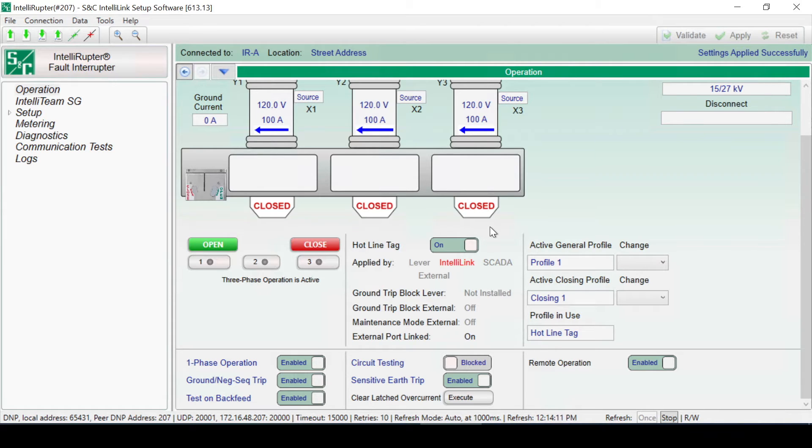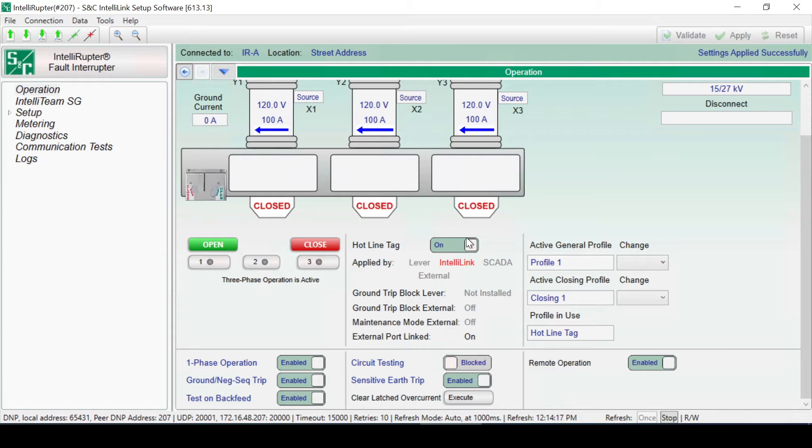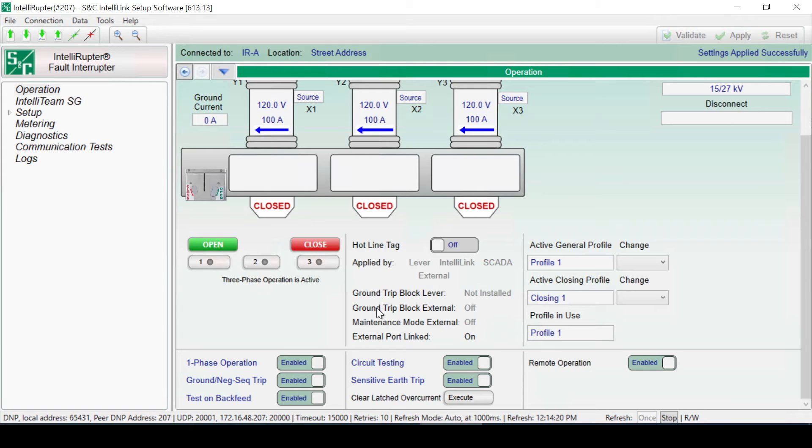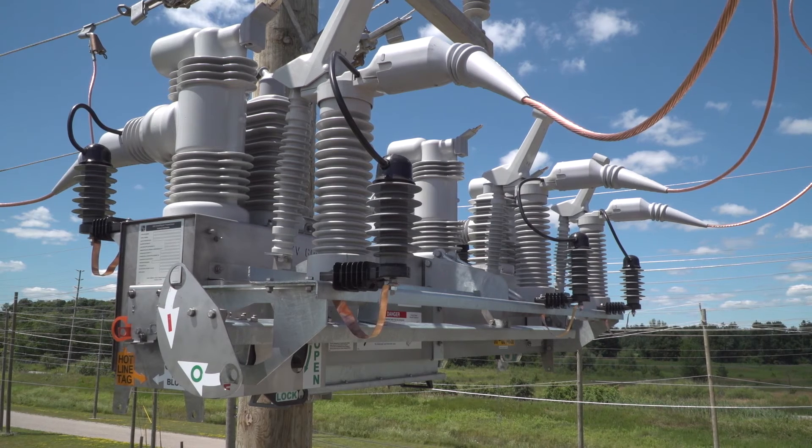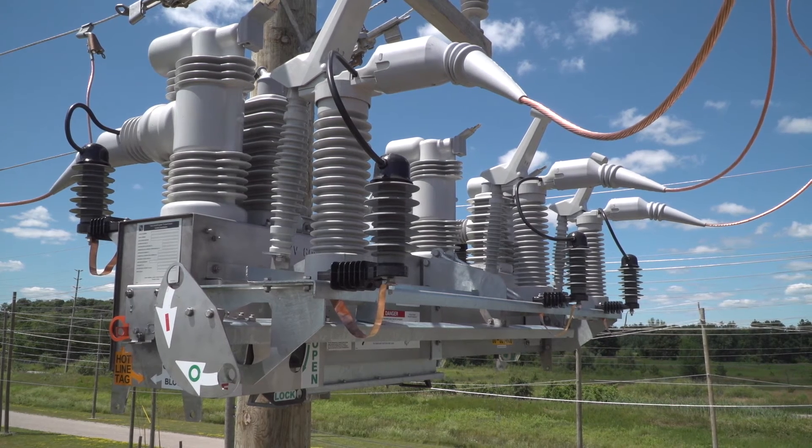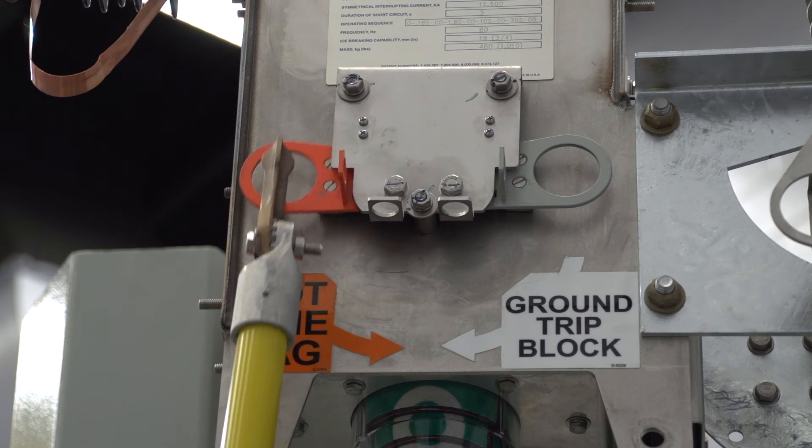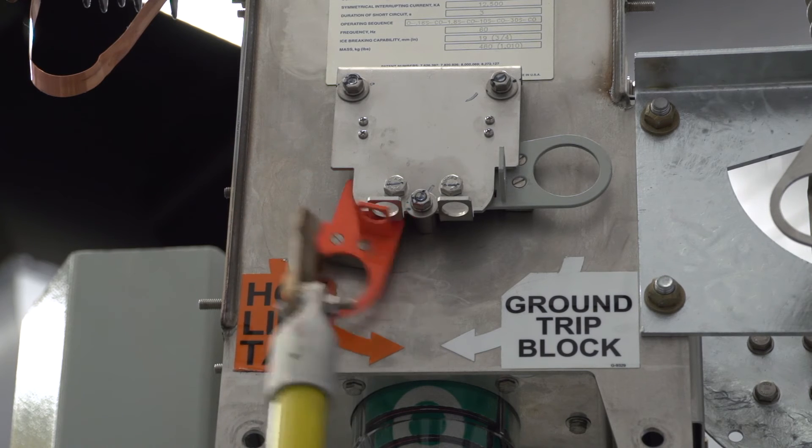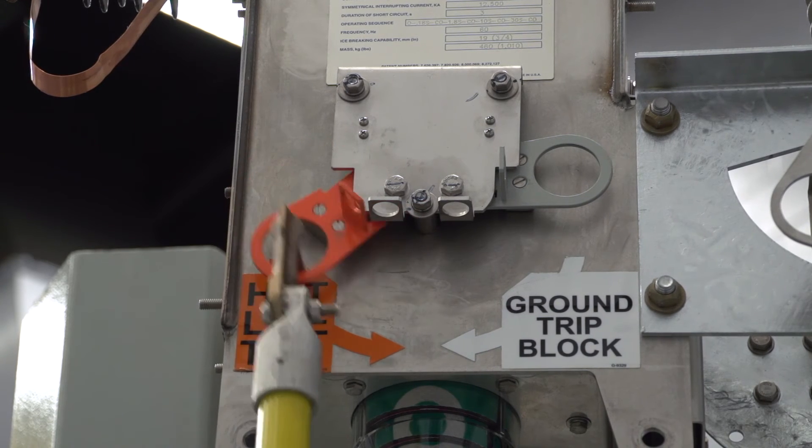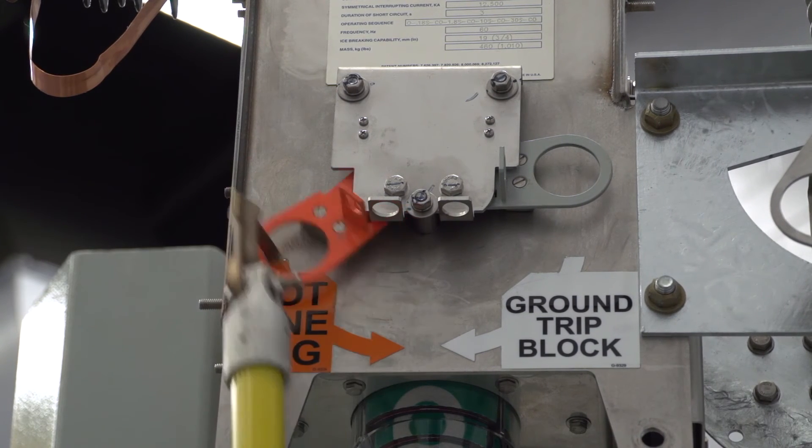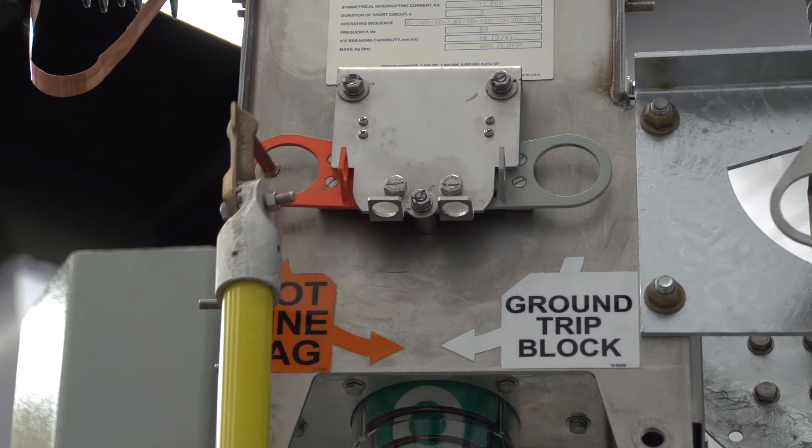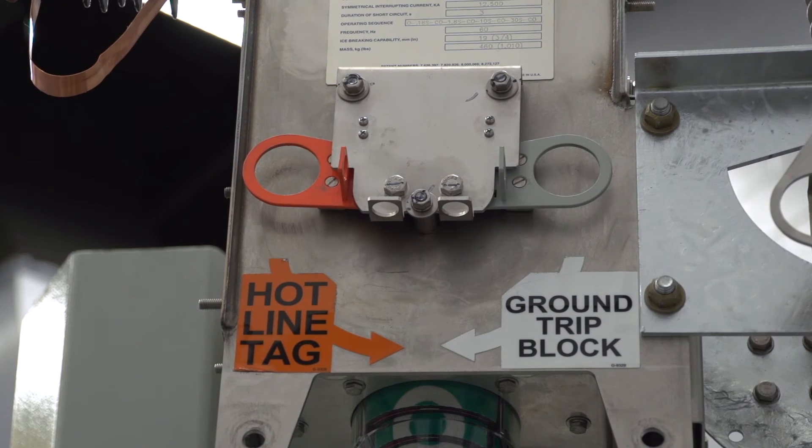An IntelliLink setup software hotline tag can only be removed using IntelliLink software or the hotline tag lever. The SCADA hotline tag can only be removed by SCADA or the manual lever, and the lever hotline tag can only be removed by the lever. To remove an IntelliLink or SCADA hotline tag with the lever, cycle it on and off twice. More than one hotline tag can be applied at a time.